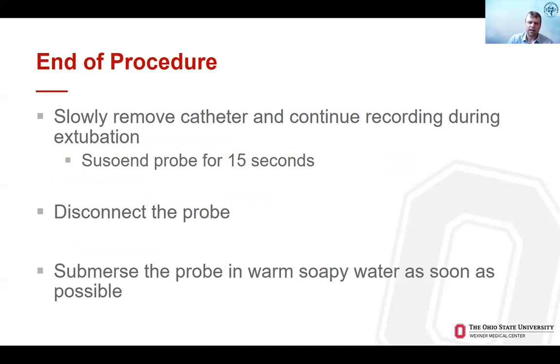At the end of the procedure, you want to slowly remove the catheter and then suspend the probe for 15 seconds. Following this, disconnect the probe and wash it in warm soapy water as soon as possible to keep everything clean and working.